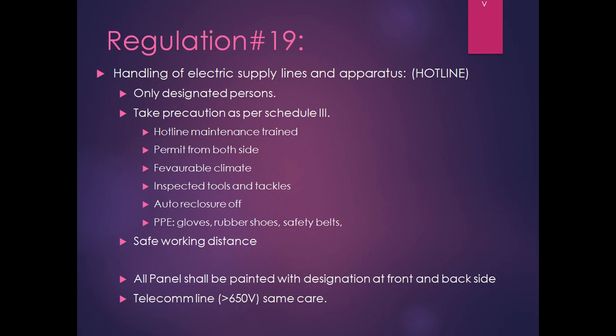The weather should be favorable condition. That means preferably it should not be hugely raining, it should not be very humid weather. The tools and tackles, whatever they are using, they shall be inspected. Auto recloser for the circuit breaker should be kept off. The working person shall use the PPEs, that is personal protective equipments like gloves, rubber shoes, safety belts, etc. They shall also maintain safe working clearance.